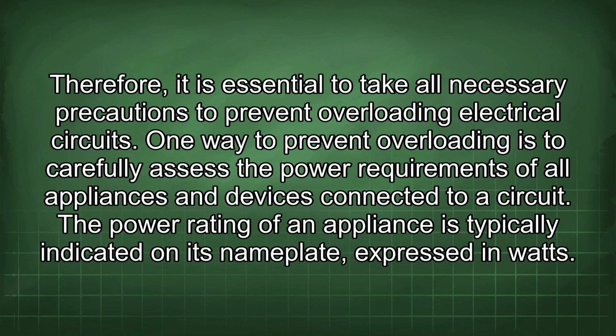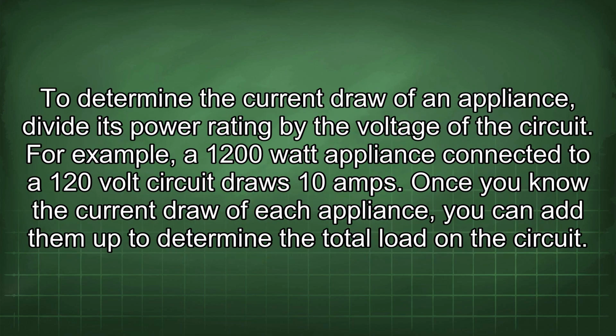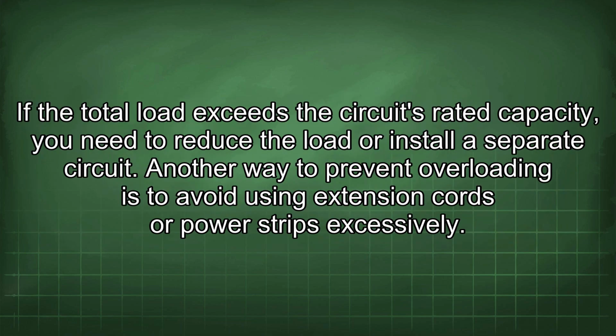One way to prevent overloading is to carefully assess the power requirements of all appliances and devices connected to a circuit. The power rating of an appliance is typically indicated on its nameplate, expressed in watts. To determine the current draw of an appliance, divide its power rating by the voltage of the circuit. For example, a 1200 watt appliance connected to a 120 volt circuit draws 10 amps. Once you know the current draw of each appliance, you can add them up to determine the total load in the circuit. If the total load exceeds the circuit's rated capacity, you need to reduce the load or install a separate circuit.